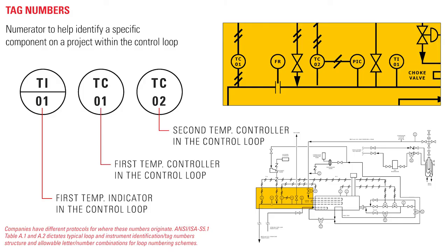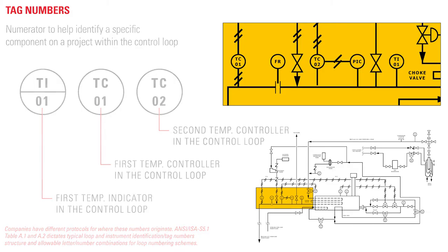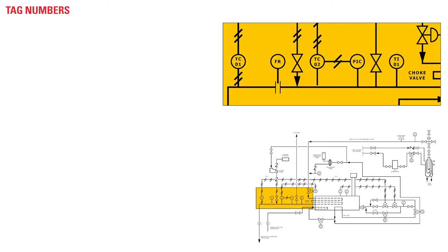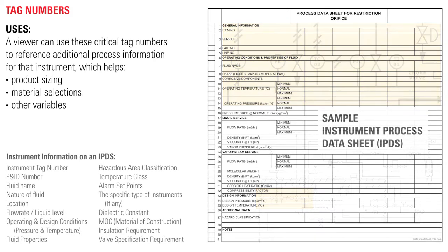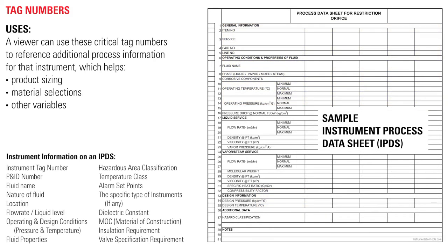If you were looking at a list of the controls, you could look at the control loop number to find that specific device on the P&ID. A viewer can use these critical tag numbers to reference additional process information for that instrument, which helps product sizing, material selections, and other variables.